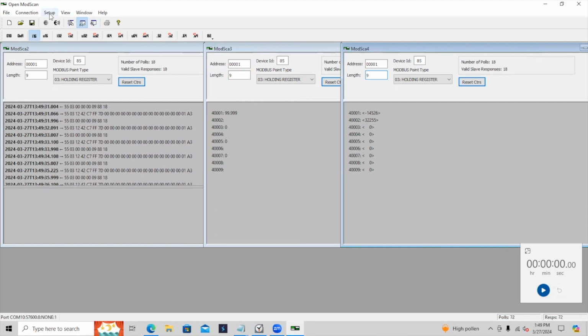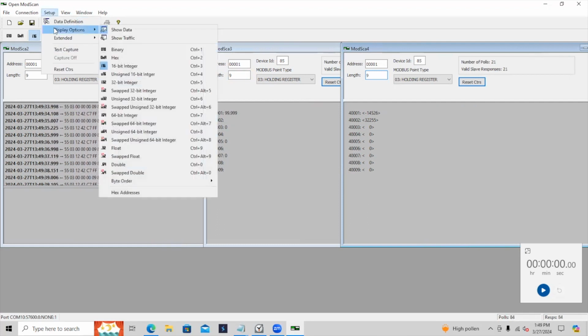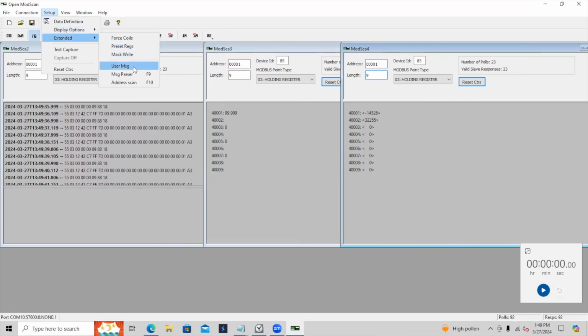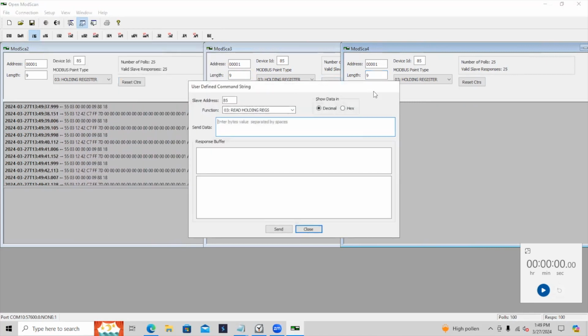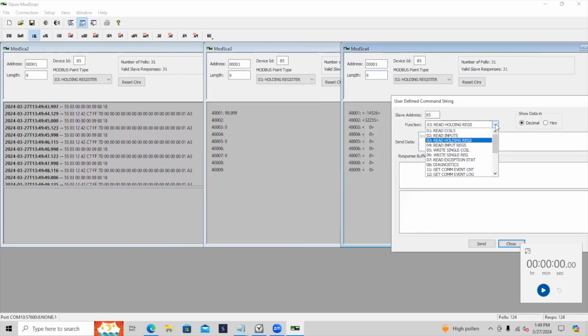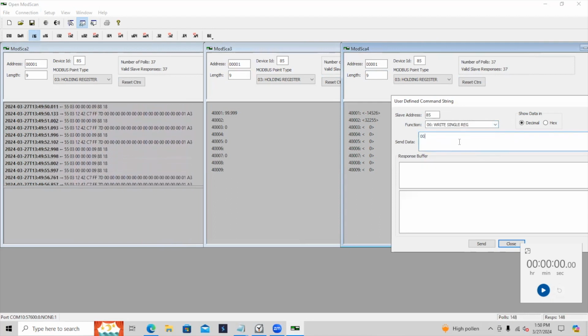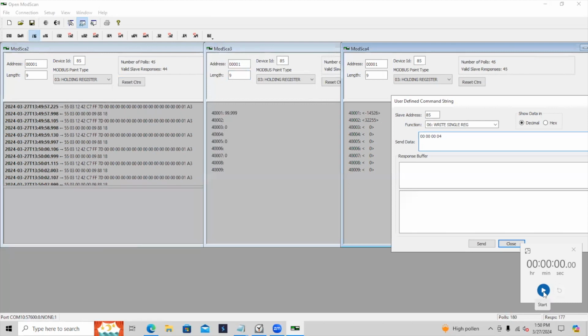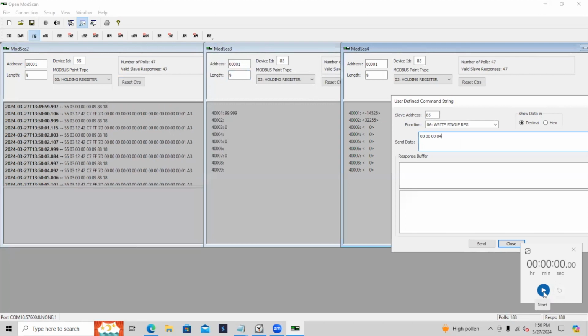We're now going to send a start command to the sensor. We do the extended user message, using the 06 write register, single register. We're going to send the 04 command. We're just going to show our timing, so I'm going to start the timer in the corner, so then you can see when the temperature, the pH, and the health output are displayed. We're going to send that command now. And now the scan command has been sent.